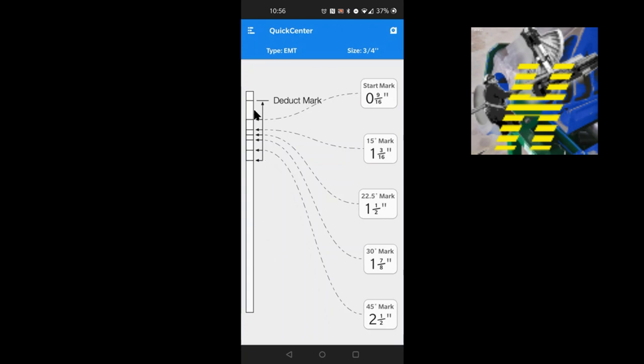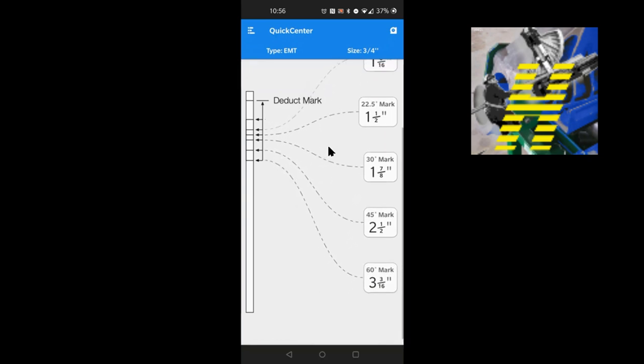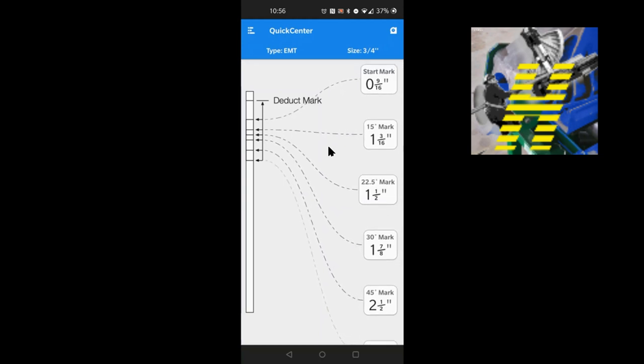On the left-hand side you're gonna see a picture of conduit with arrows pointing from all these measurements — start mark at 15, 20, 30 degrees, and you can scroll all the way up to 60 degrees. Pay attention to the left side directly under EMT — you're gonna see 'deduct mark.' All of these measurements from the deduct mark reference the arrow on the bender. On hand benders they mean the arrow; on electric and table benders, they mean the actual hook or shoe — where you line up your marks from.